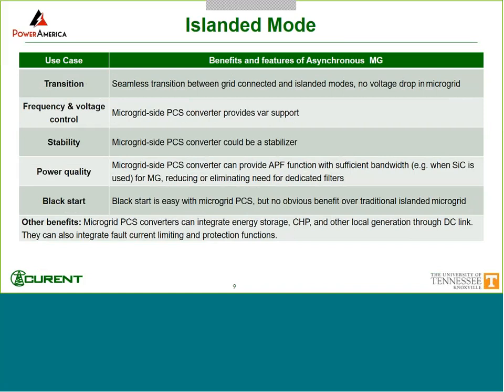And that was mainly for the grid connected mode. For islanded mode, I mentioned the transition, and also the frequency and voltage control can be done independently from the grid side converter. On stability, the microgrid side converter can actually be a stabilizer. Same thing with power quality, and black start is also very easy. And some other benefits I already mentioned in our and Anand's slides. Actually, this microgrid PCS can integrate energy storage and other local energy sources. And even the fault current limiting protection function can probably be integrated as well.